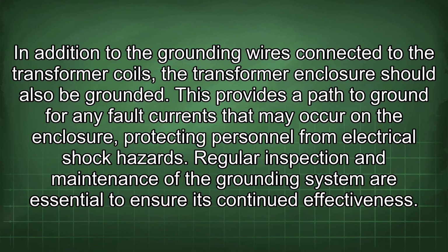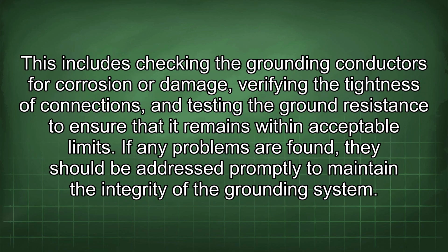Regular inspection and maintenance of the grounding system are essential to ensure its continued effectiveness. This includes checking the grounding conductors for corrosion or damage, verifying the tightness of connections, and testing the ground resistance to ensure that it remains within acceptable limits. If any problems are found, they should be addressed promptly to maintain the integrity of the grounding system.